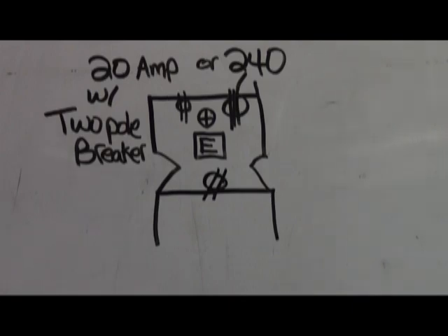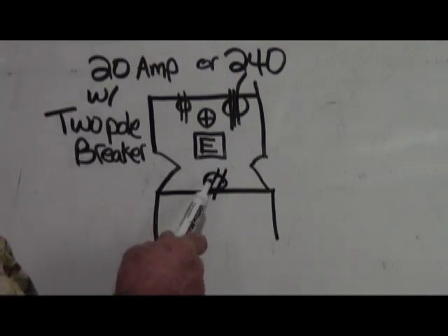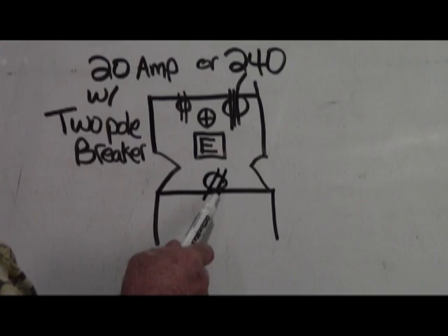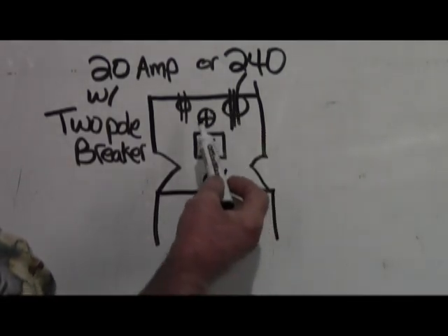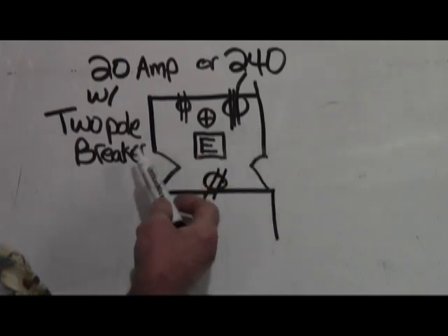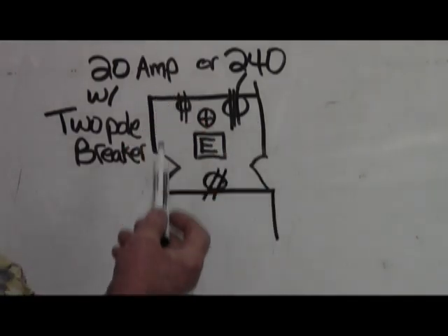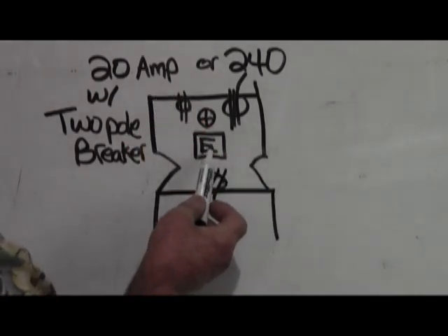Now your typical laundry room is going to have either or. First of all, it has to have a service outlet, and that's got to be GFI protected. Generally that is opposite of your washer and dryer unit. It's got to have a light, and it's got to have an exhaust fan.